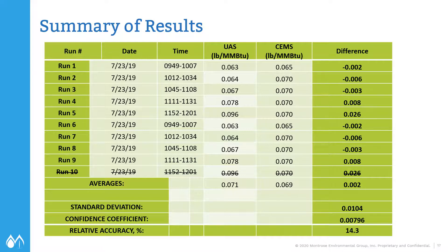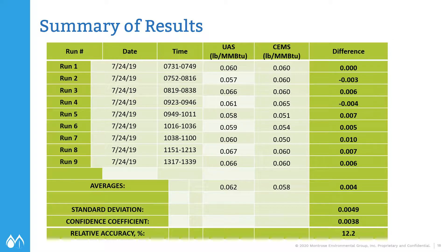This is what a RATA table looks like. For the calculations, you use 9 to 12 runs — for day one, I took our five runs and copied them down to make ten runs. The column marked CEMS was the plant continuous emission monitoring system, with units in pounds per million BTU and an average of 0.069. The drone averaged 0.071 pounds per million BTU, resulting in a relative accuracy of 14.3%, which met the EPA requirement of 20%. For day two, similar results on a different source: the CEMS average was 0.058 pounds per million BTU, the drone sensor package averaged 0.062 pounds per million BTU, and the relative accuracy was 12.2%, which again met the EPA requirement.